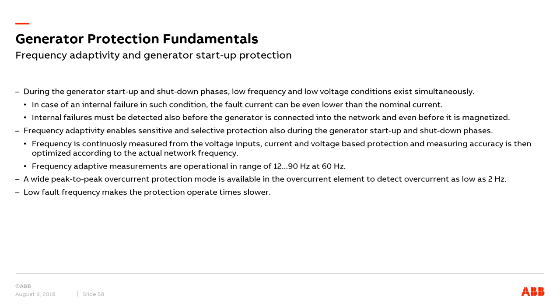That is very critical because we don't want a faulty generator to go into the system, which can cause more serious damages. So the frequency adaptivity enables sensitive and selective protection during generator startup and shutdown phases. So here the operating range is typically from 12 to 90 hertz at 60 hertz. Okay.